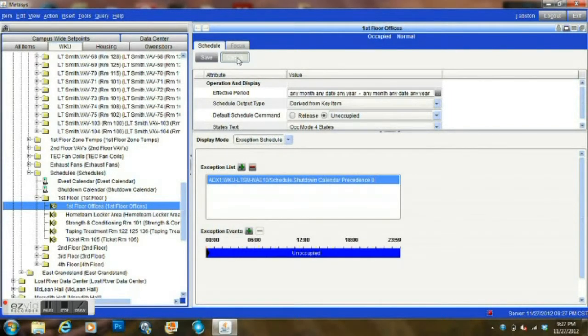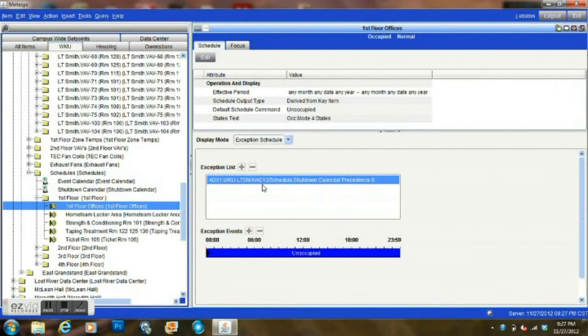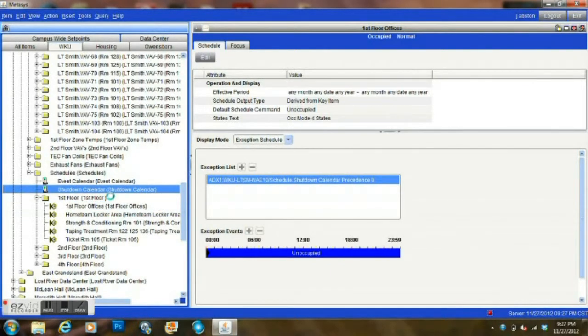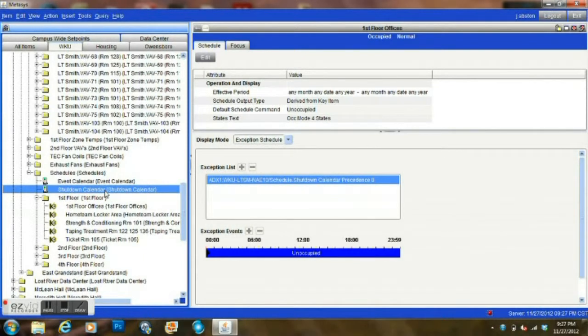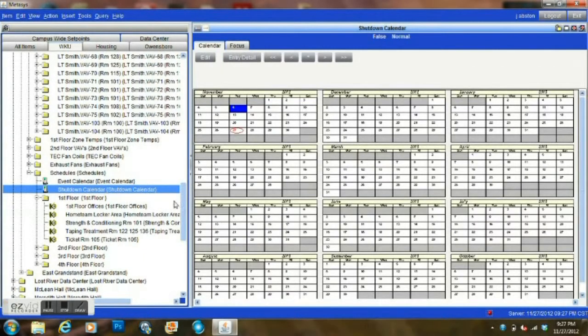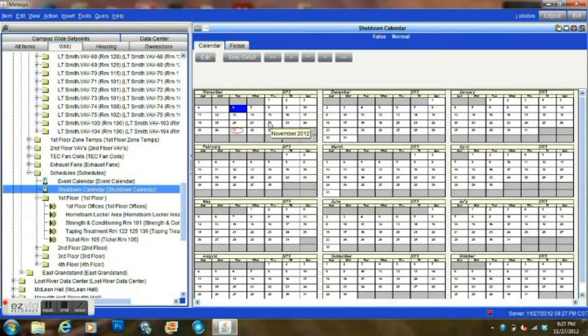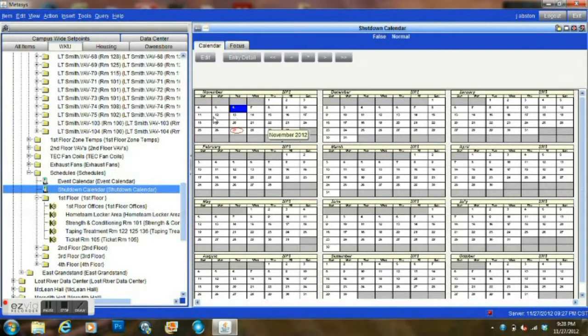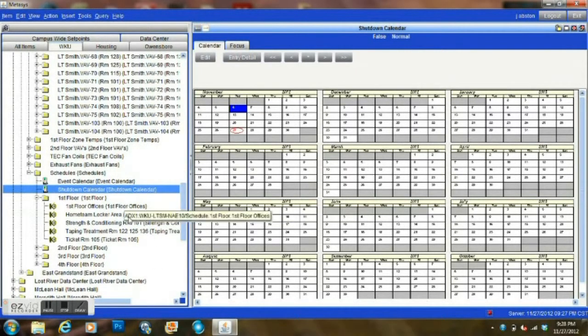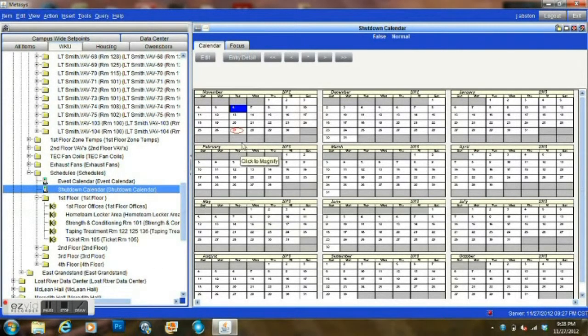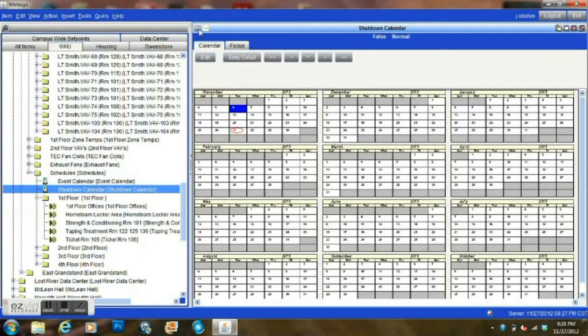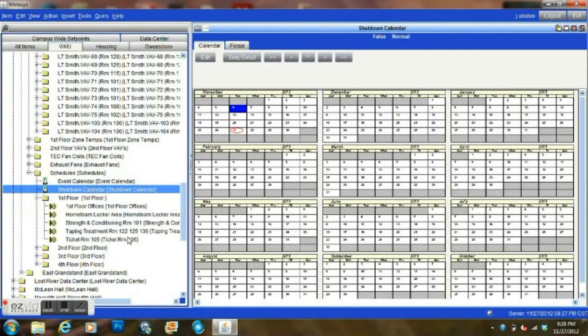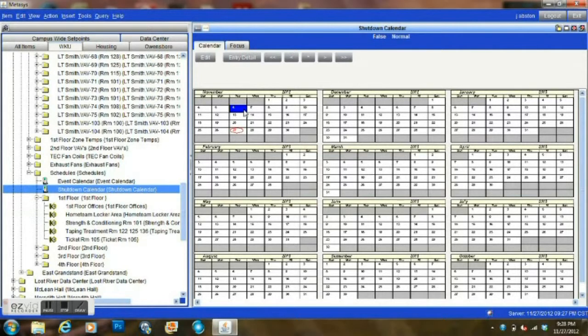As you see here, this is a calendar reference here. We can see that this calendar is actually this one here. This is our shutdown calendar. Now these work exactly like an exception schedule. If you were to go in and put in a particular day or whatever, you can do a series of schedules, and all those schedules can then be tied to the same calendar instead of having to go into each individual schedule and set up a particular runtime.